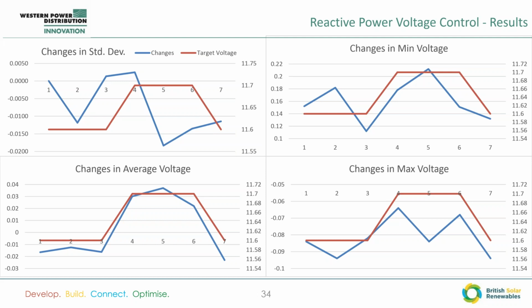However, we took several nights' worth of data from nights when we weren't testing, and we were looking for a pattern. So I set the voltage. It reads artificially high, 11.6, 11.7. That's due to the PQM reading error. That's not actually what the battery was trying to achieve, but we're looking for a pattern that follows the red line that demonstrates the target voltage.